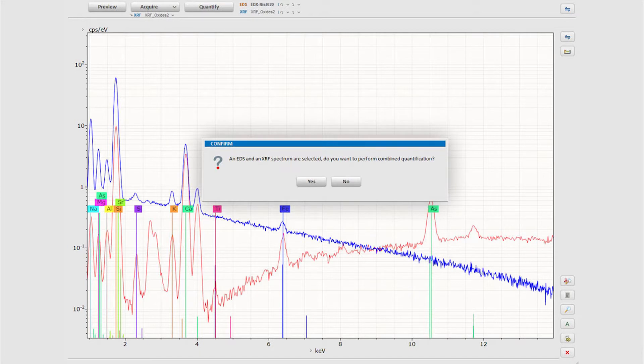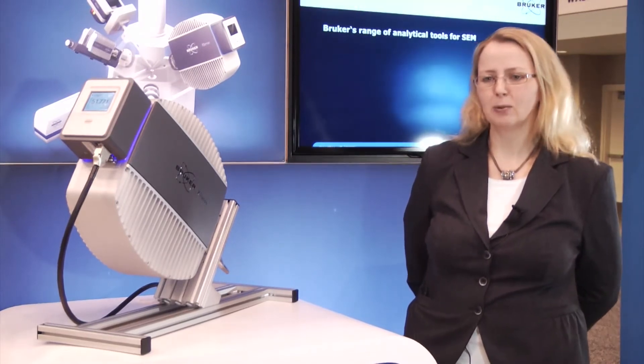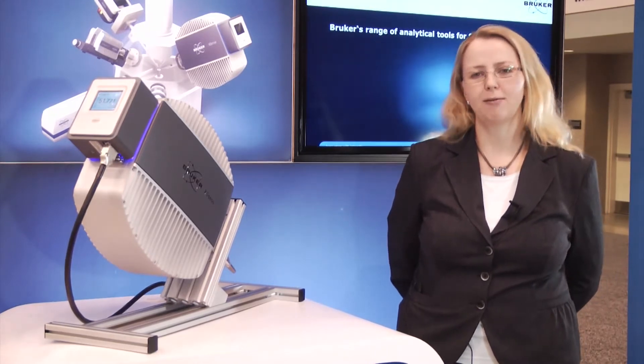This enables us to analyze the same area with EDS and micro X-RF. Micro X-RF is an energy dispersive technique so we are using the EDS silicon drift detector to collect the incoming X-rays produced by fluorescence.